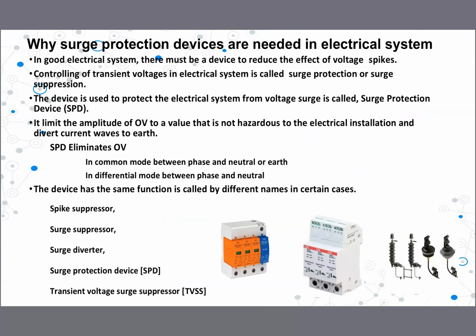There are two methods that an SPD uses to reduce the amplitude of voltage to a non-hazardous level. The first is common mode. If you take an electrical circuit, it's like this. We have a load, then we have an earthing point here. This is live, this is neutral. In common mode, it discharges between live and earth or neutral and earth. There is another mode called differential mode. In differential mode, it discharges between the phases or between phase and neutral. That is how it works.